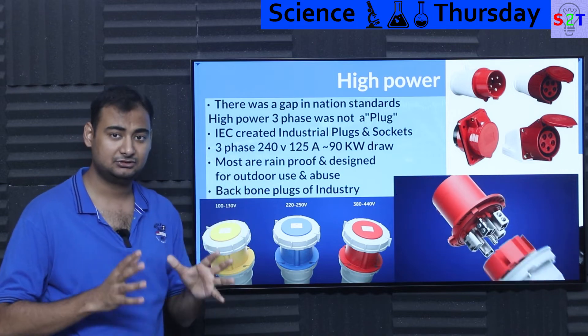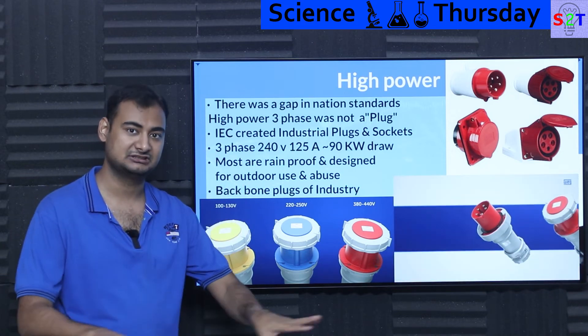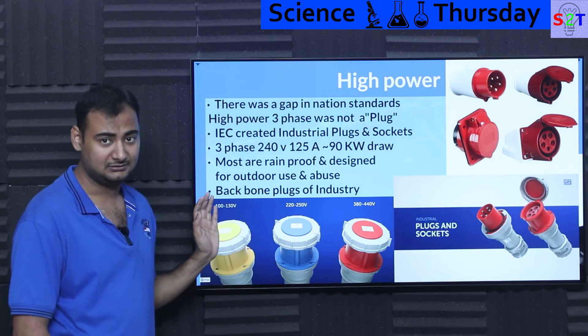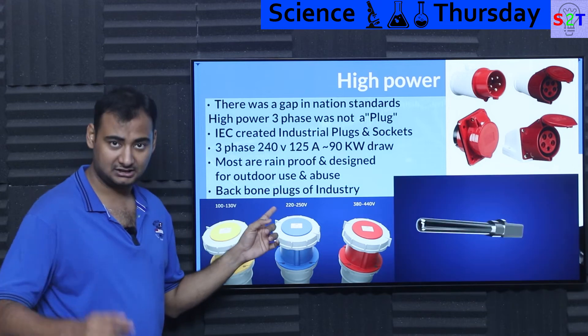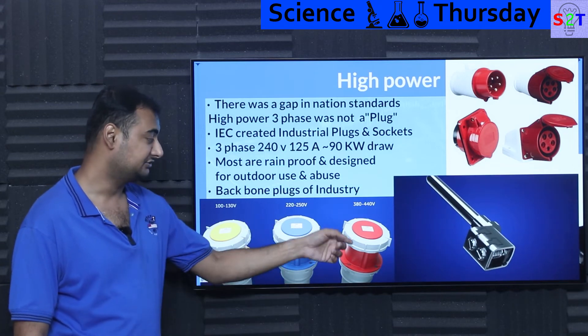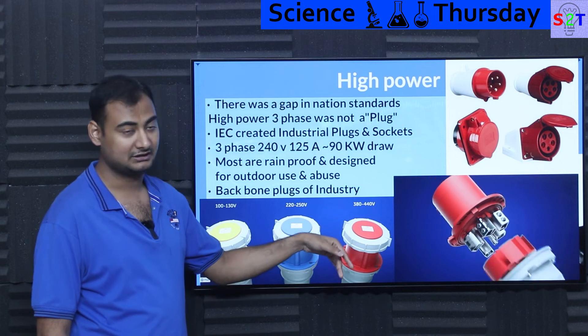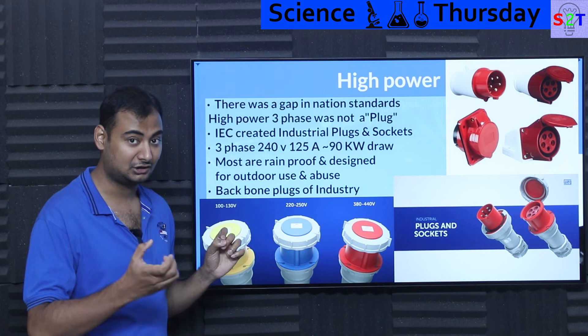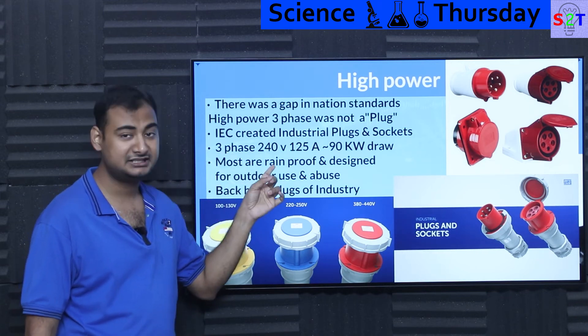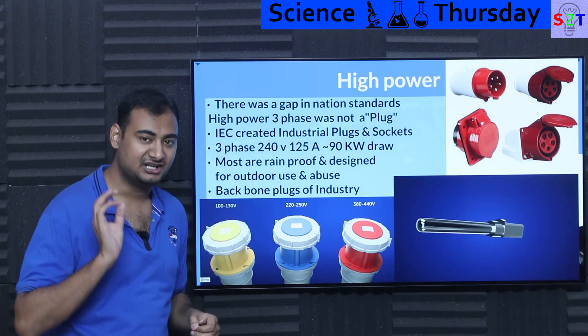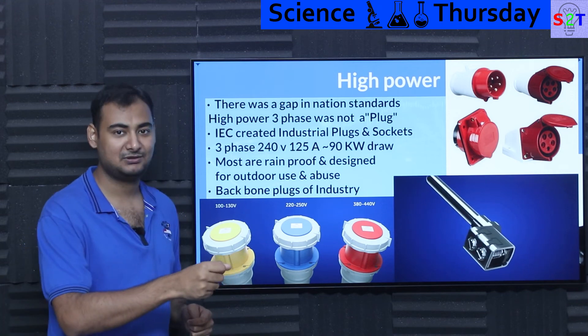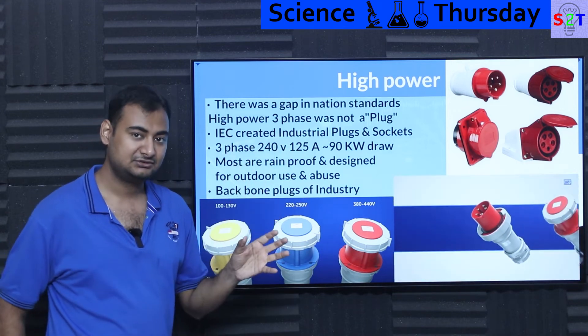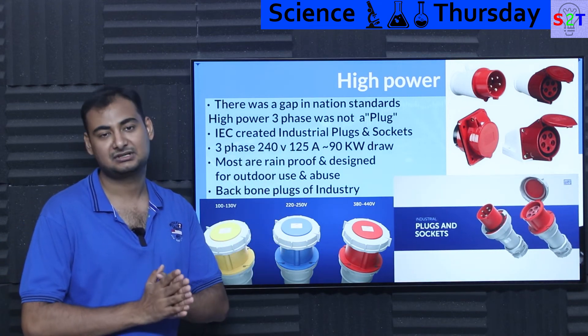This gap gave the IEC a very good opportunity to standardize high-power three-phase connectors across the planet. The color coding is: yellow for below 130 volts, blue for single-phase 220–250 volts, and red for 380–440 volts three-phase. At maximum capacity, the largest connectors support 240 volts at 125 amps — roughly 90 kilowatts — meaning you can plug in and out an entire generator's worth of power.